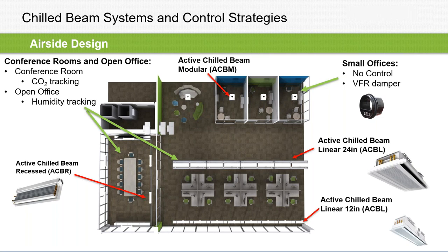So just to reiterate that point, it's really important to monitor your space dew points and know what those are. And if you're bringing in water colder than that, that's going to cause some problems. So definitely dehumidify the space. Definitely on startup, maybe Monday morning, bring the air on first, especially after the building is just getting started up. You just closed the facade of the building. There could be a lot of moisture in there, so definitely monitor your dew points before you bring the water in. So great points.